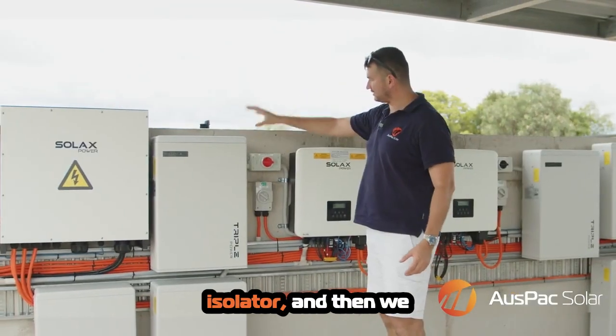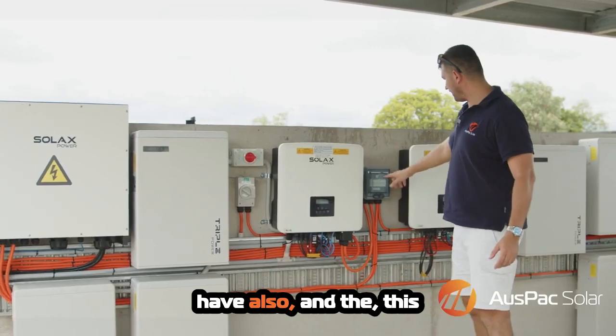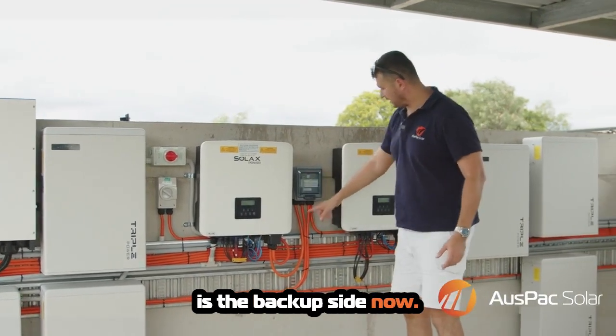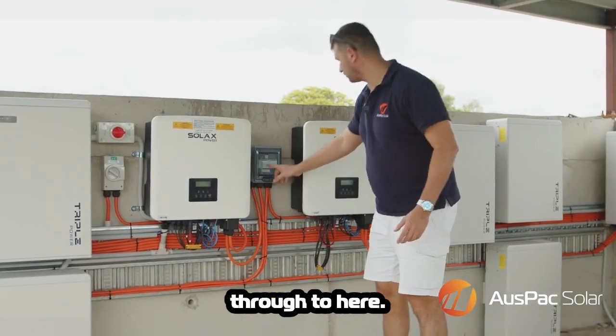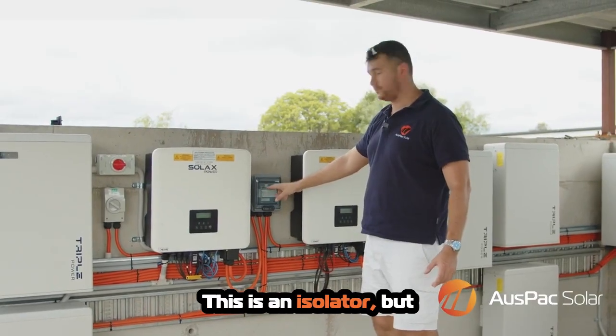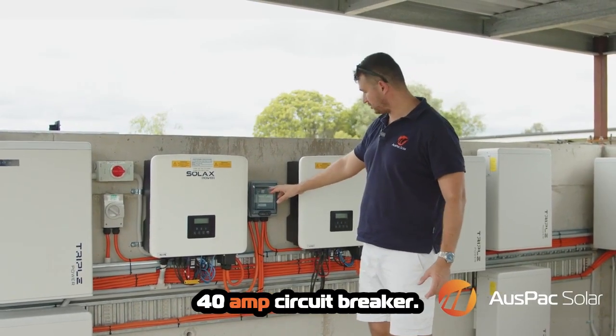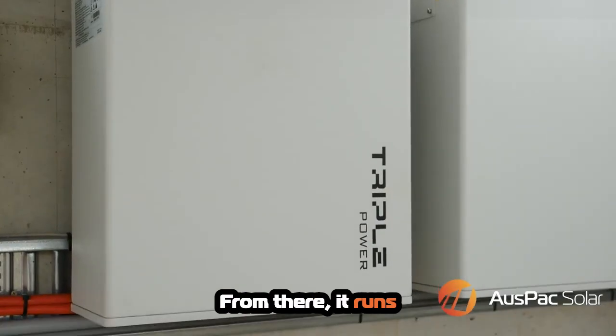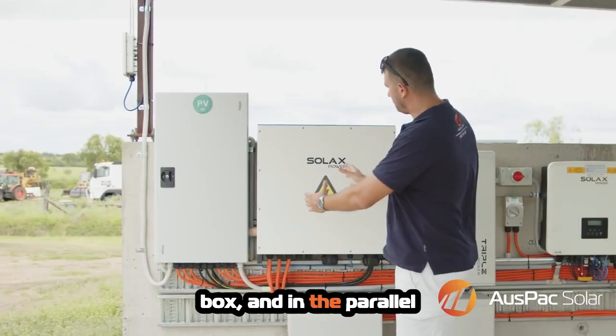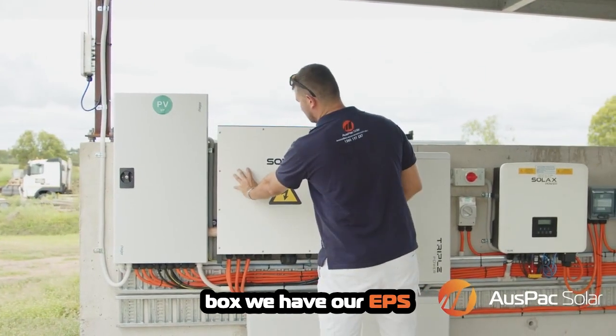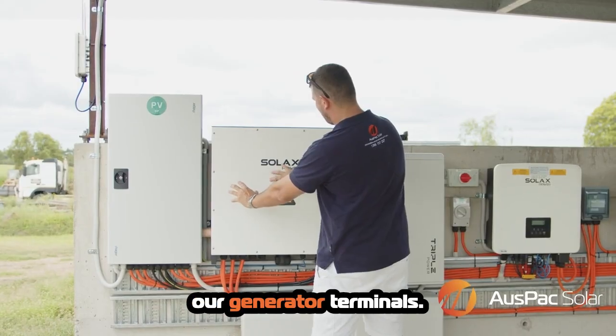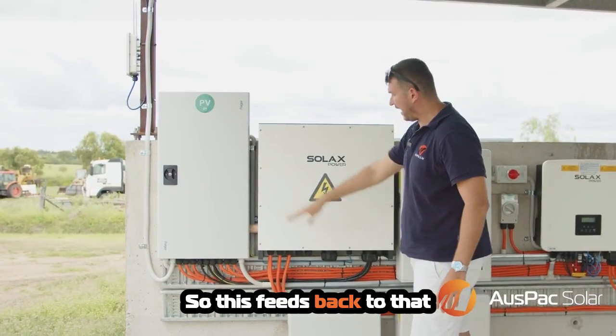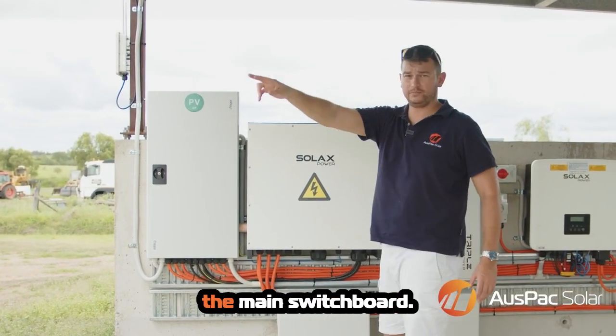We have the battery isolator, and then we have also, and this is the backup side now, so from the backup terminals it runs through to here. This is an isolator but also a circuit breaker, so a 40 amp circuit breaker. From there it runs back to this parallel box, and in the parallel box we have our EPS terminals and we have our generator terminals. So this feeds back to that switchboard, which feeds the main switchboard.